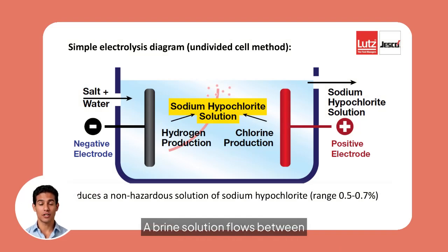This diagram shows undivided cell electrolysis. A brine solution flows between negative and positive electrodes. When DC power is applied, chlorine and hydrogen gases are produced and react with the brine to form a dilute sodium hypochlorite solution, typically 0.5 to 0.7%, which is safer to store and handle.